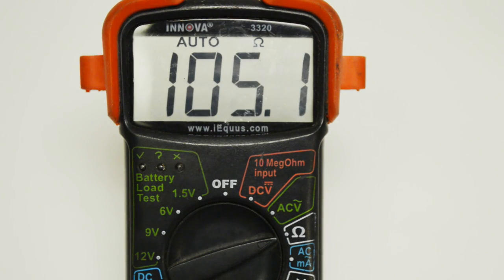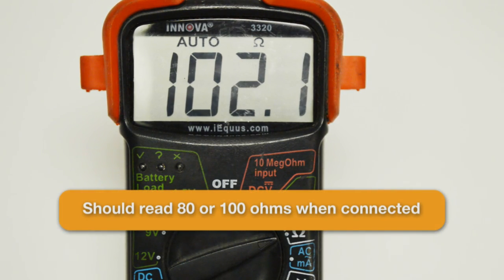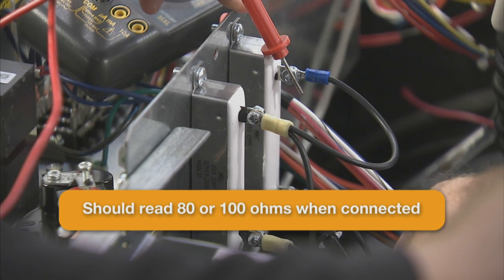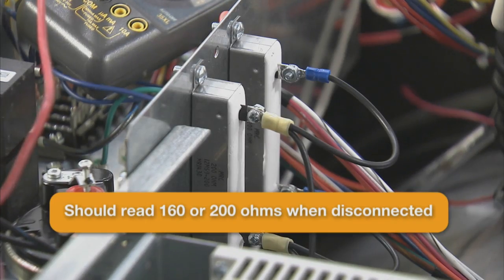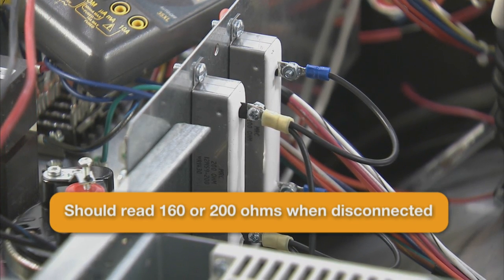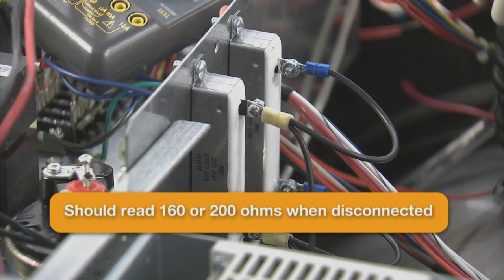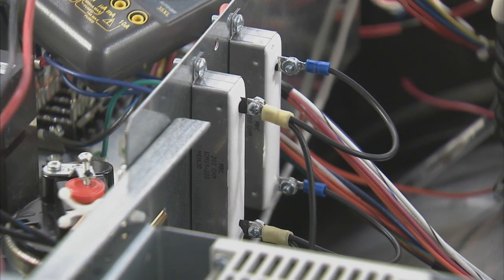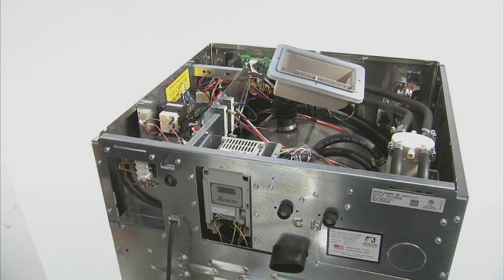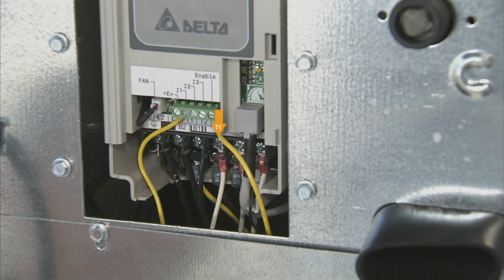With the wires connected to the braking resistor, the reading should be 80 or 100 ohms depending on the model of machine. With the wires disconnected from the braking resistors, the readings will be 160 or 200 ohms, depending on the size of the machine. If the readings are outside of these parameters, the braking resistors will need to be replaced. The last step before installing a new VFD is to check the motor winding resistance. You can locate the T1, T2, and T3 motor leads on the terminal block of the VFD.